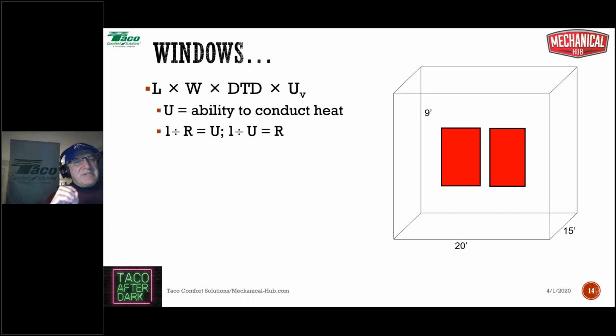So now it's length times width times design temperature difference. Length times width is area, times design temperature difference, times the U value of the window. Now, we talked about U value a little bit earlier - it's the ability of a material to conduct heat. So when we're talking about U values for windows and for wall assemblies or whatever, we don't want a big U value, we want a little U value. We don't want to conduct heat very well from one side to the other.